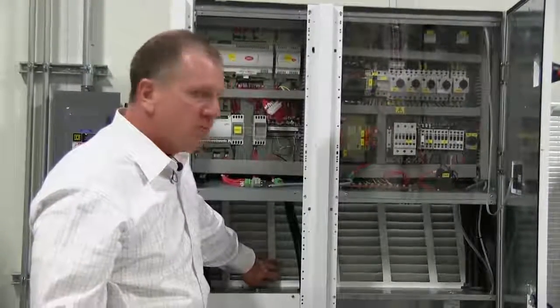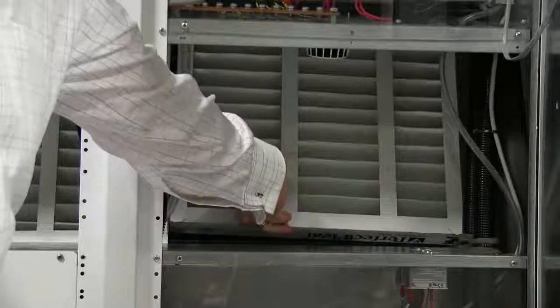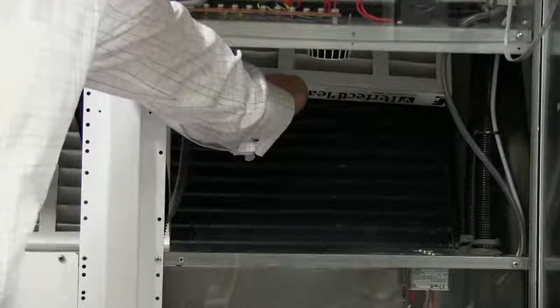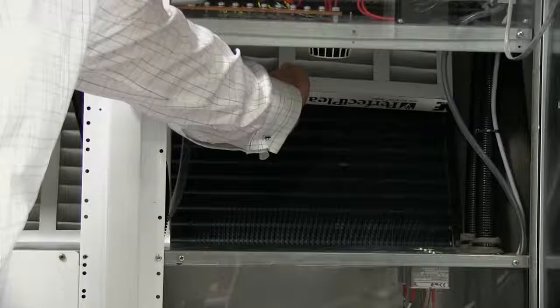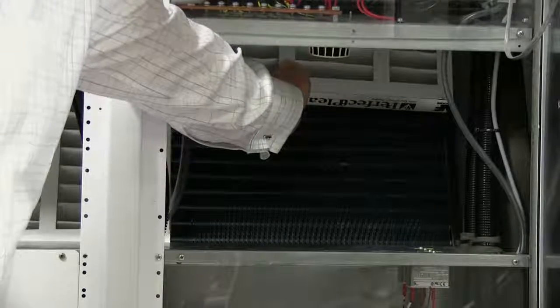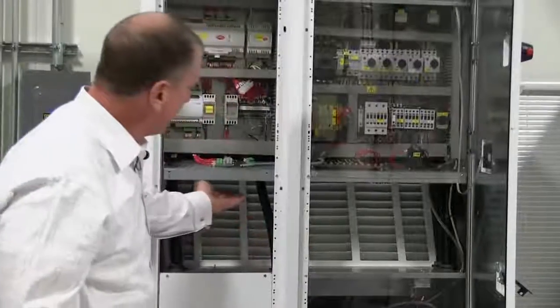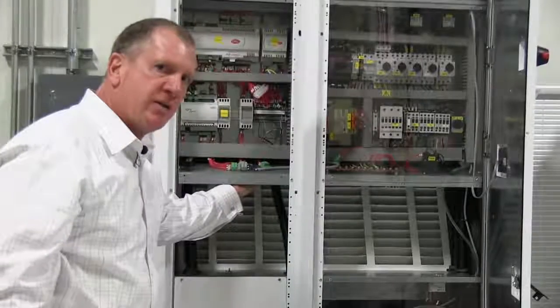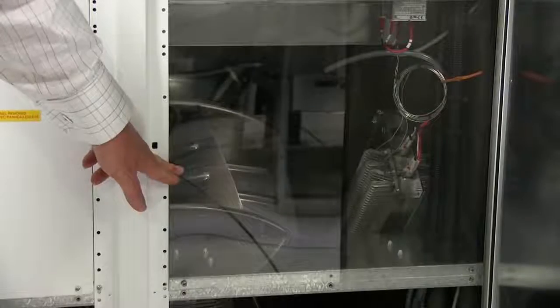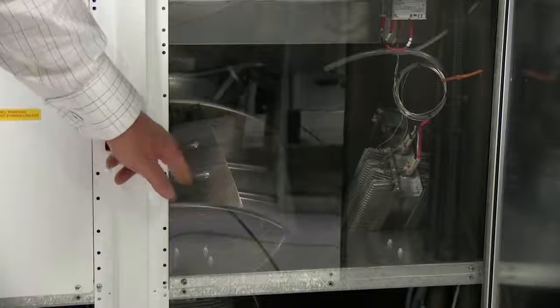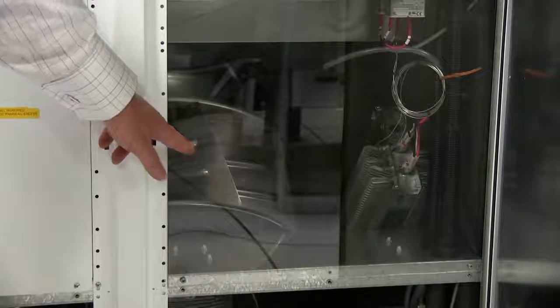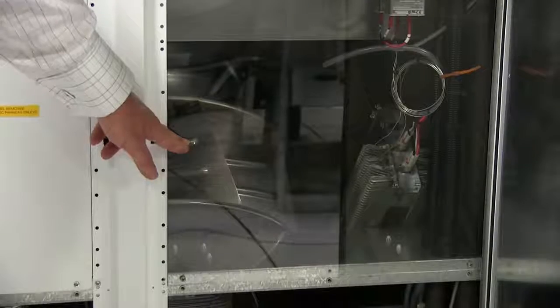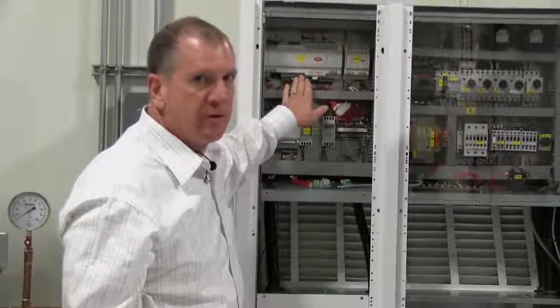The units are all equipped with MERV 7 filters. Standard also is a blue fin or hydrophilic coated coil. This coil improves fin longevity up to 3 times and also improves the drainage of condensate. The temperature humidity sensor is located within the airstream on the underside of the electrical panel. Standard also is the EC, or electronically commutated, blower. This blower motor is 40% more efficient than standard motors, and as it's direct drive, it eliminates belts and pulleys and reduces maintenance. It also facilitates ease of adjustment of CFM and static pressure on startup by the startup technician using the programmer display.